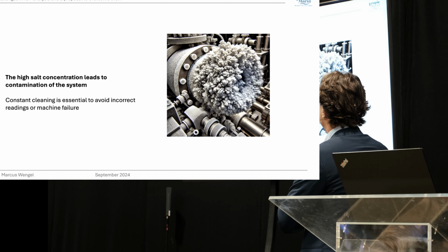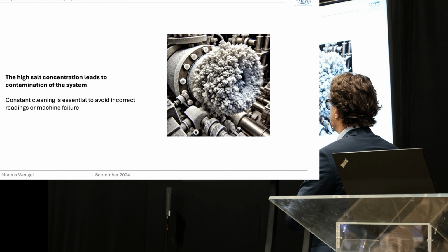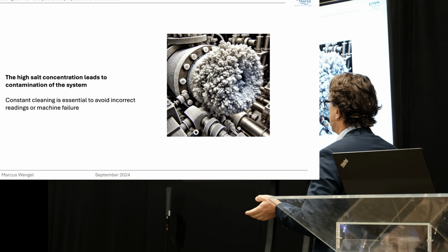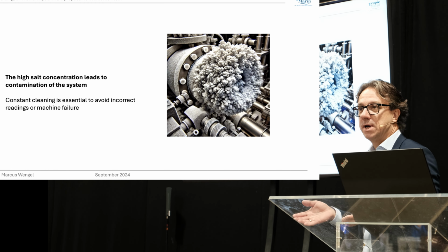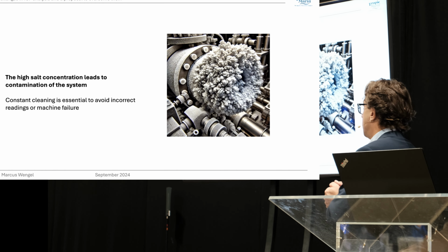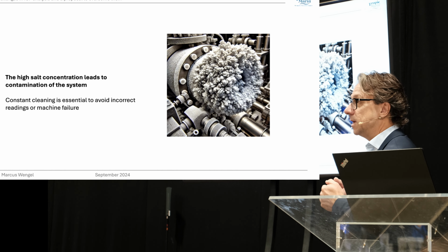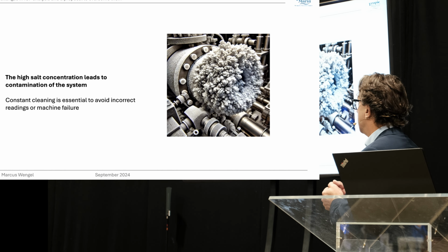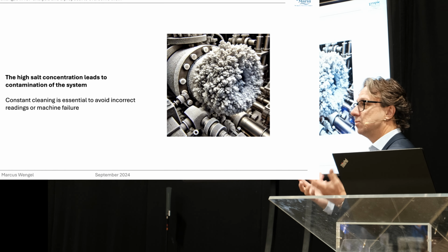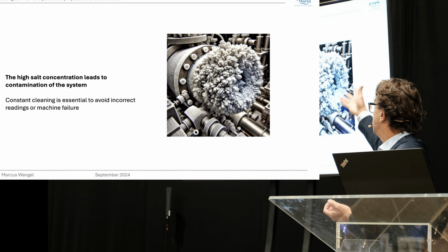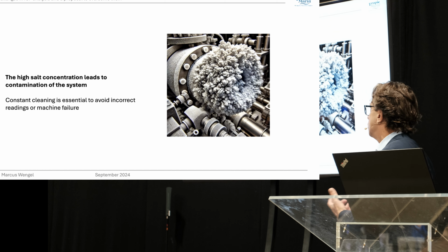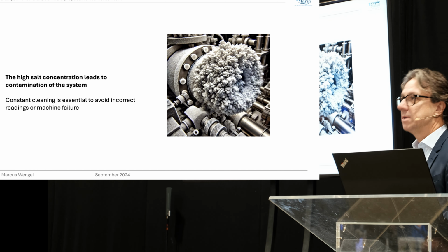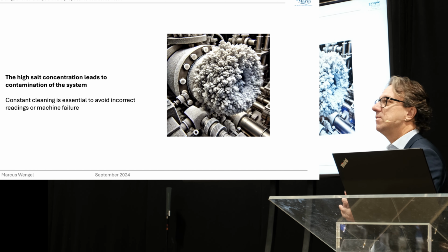One more thing which is also important: we work with high salt concentrations. We have 3.5% salt in our tanks, so this can easily lead to salt contamination in the system. We dry this water out, so we get these plugs there. So cleaning is one of the most important things, but everybody wants to get his sample very fast.